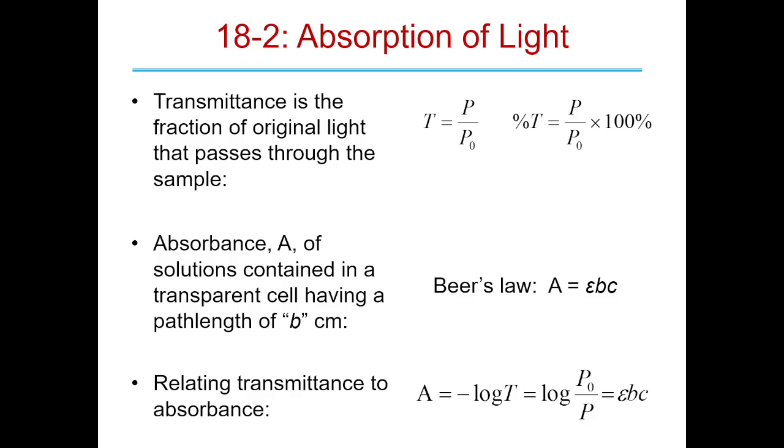Notice that in the spectra you've been taking in lab, if you go back through them, you'll actually see places where you have higher than 100% transmittance. What did that mean? You got more than P0 back out, didn't you? Yeah. And that's because the P0 is set by the background, and so your background's in error, or you have a different condition.